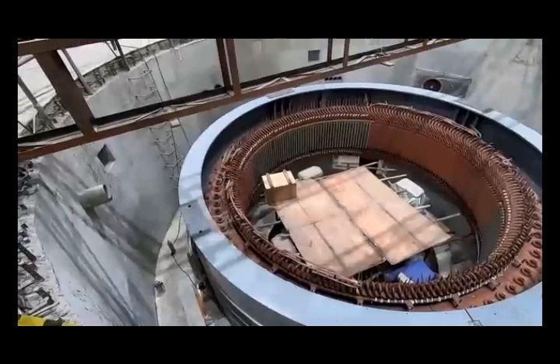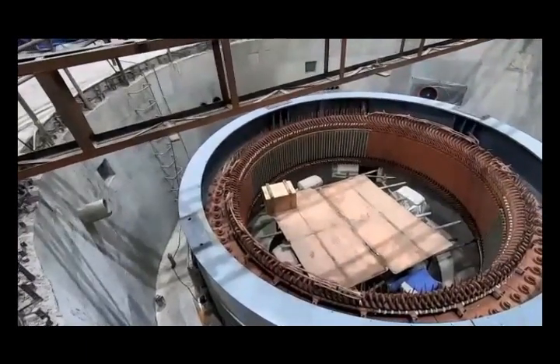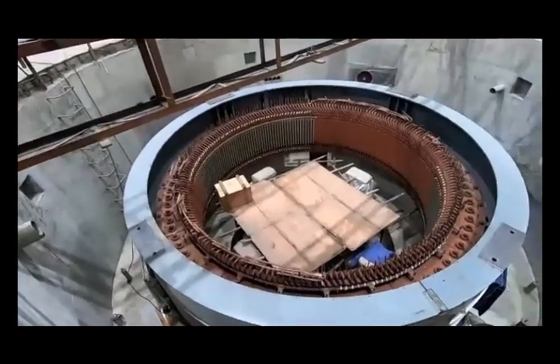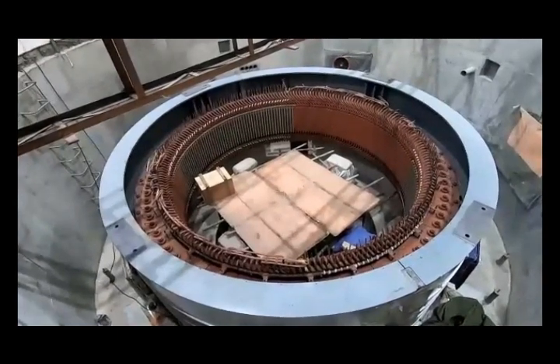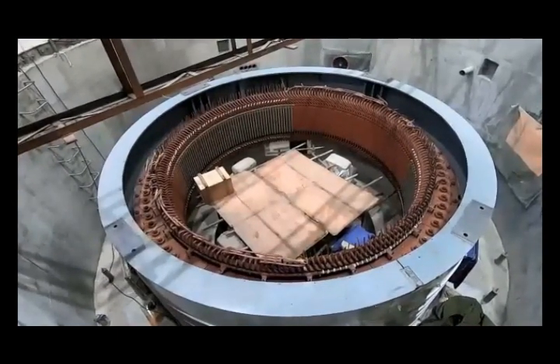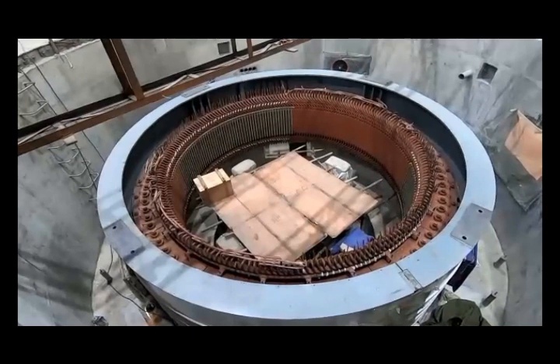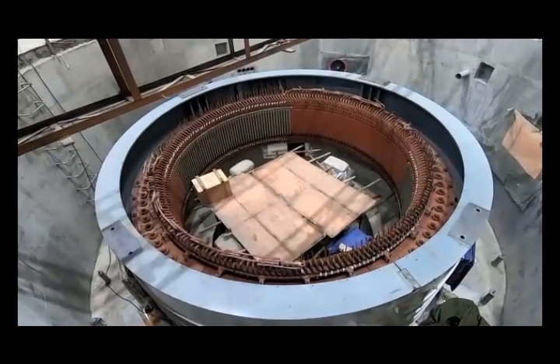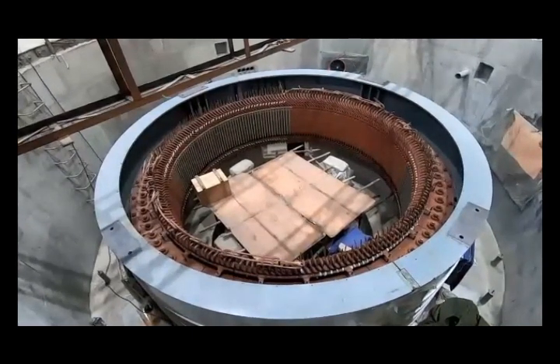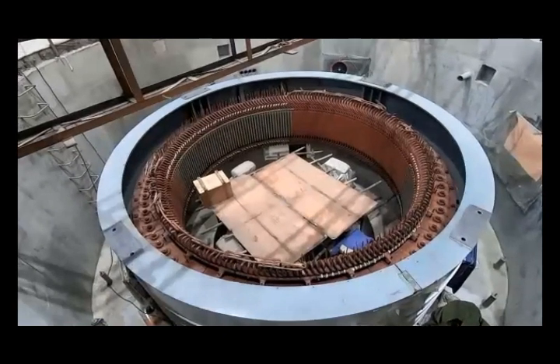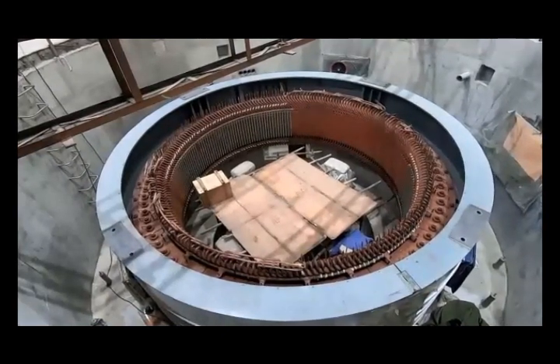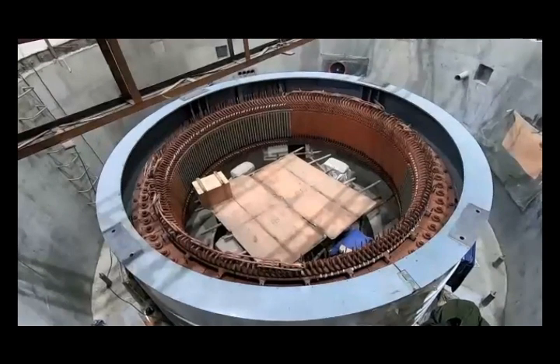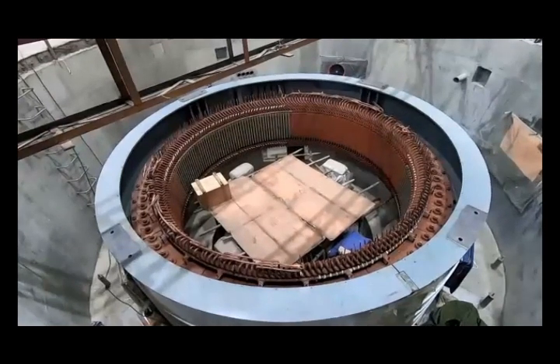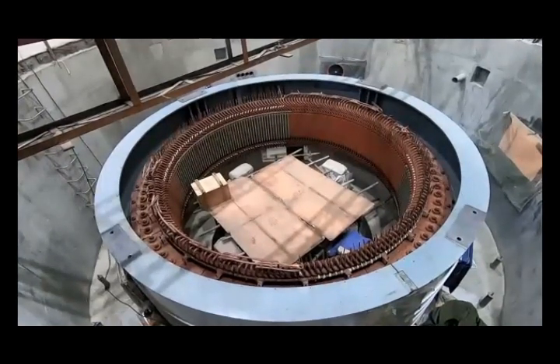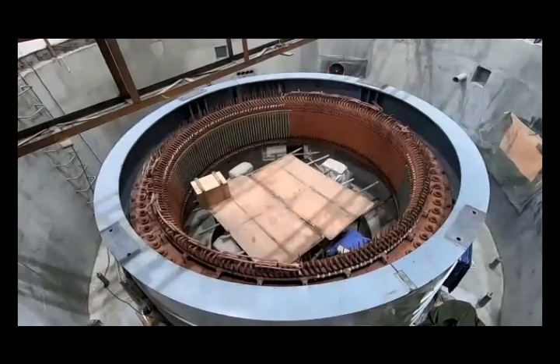The rated capacity of this generator is 17.5 megawatt, 50 hertz, 0.8 power factor lagging. The synchronous speed of the generator is 300 rpm, therefore we have 20 poles. The connection method is a star winding connection. The supply output of the generator is 11 kV and the amperage is 1148.